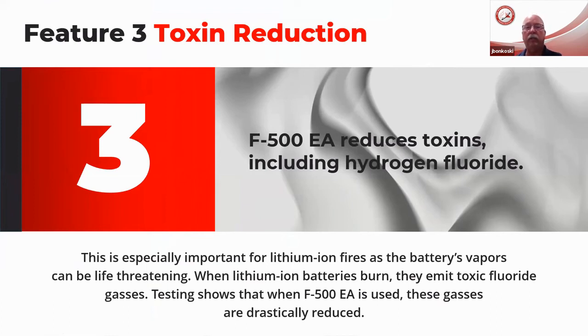So when we look at these batteries emitting these gases - in some of the testing that was done, there was a gentleman using those extinguishers. When we saw those previous videos of the batteries burning with the dry chemical and with the foam, the gentleman extinguishing those batteries wasn't wearing an air pack, wasn't wearing breathing apparatus. He spent some time in the hospital detoxing because of his exposure to hydrogen fluoride gas.